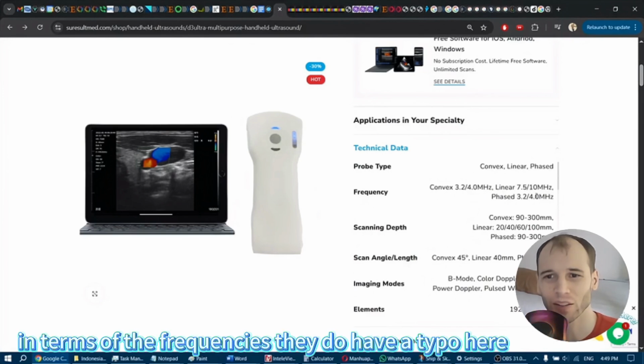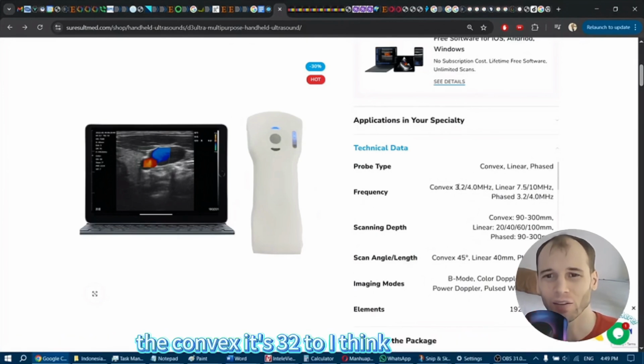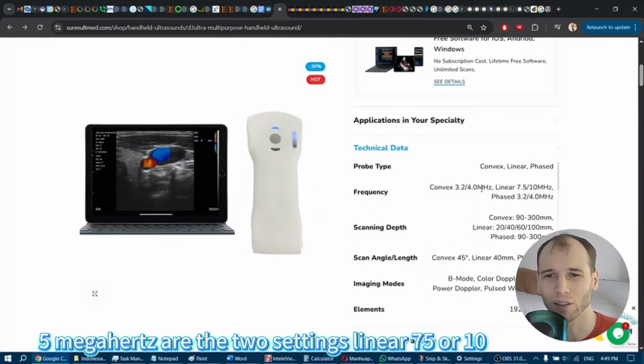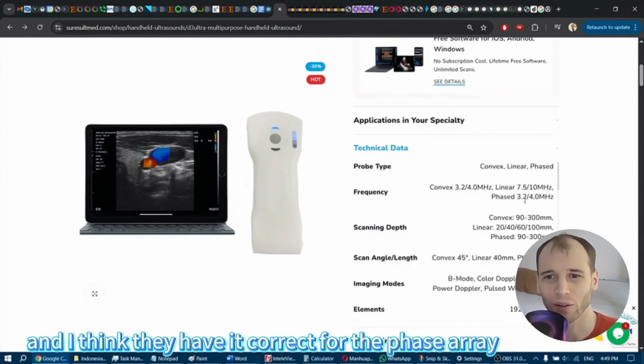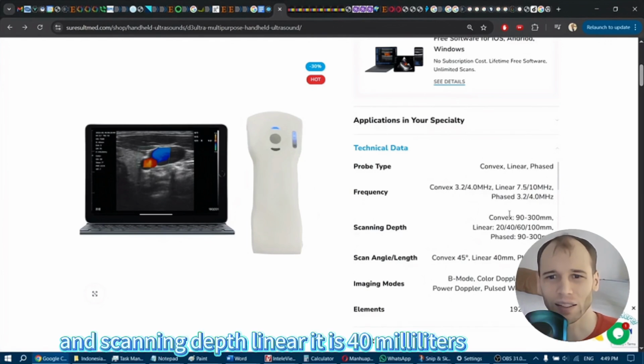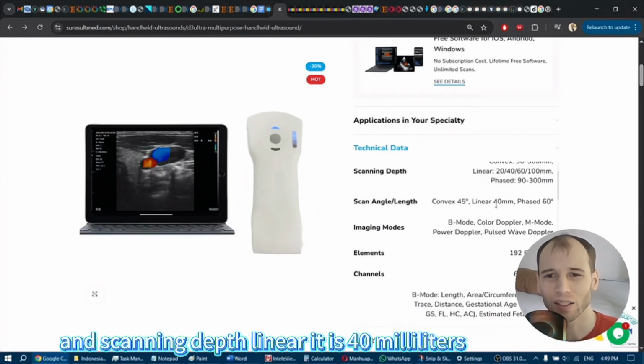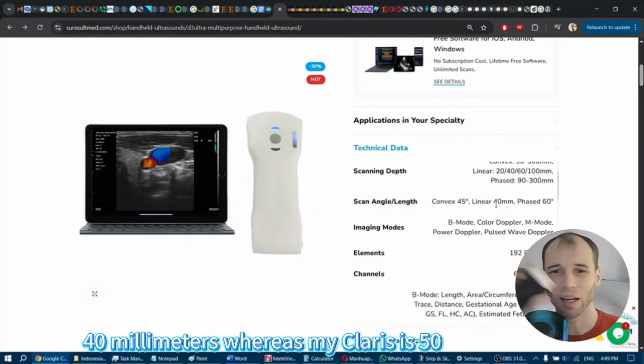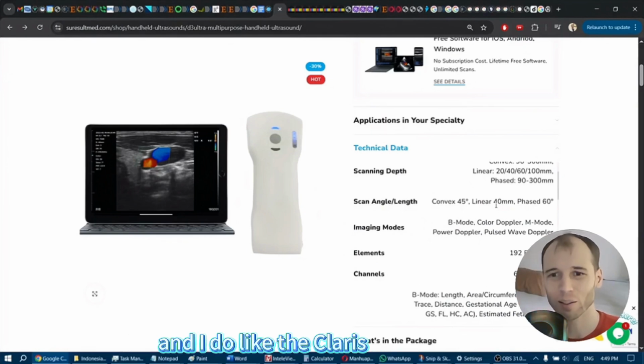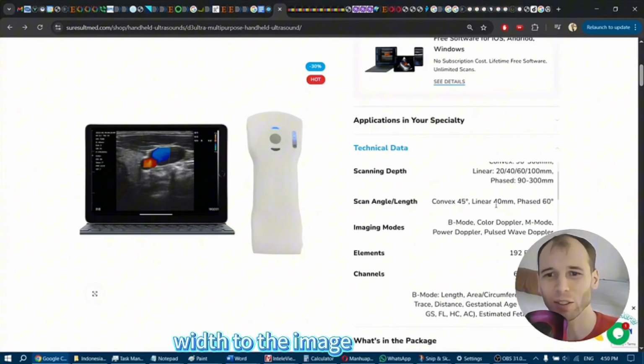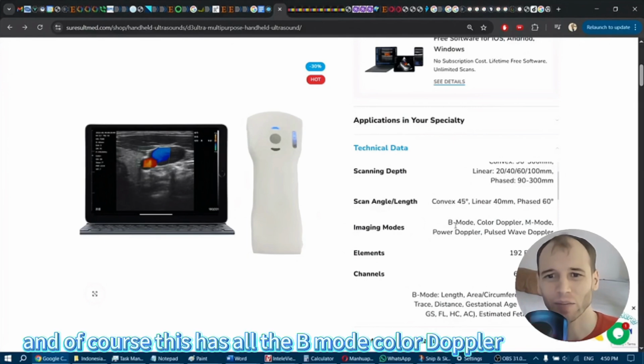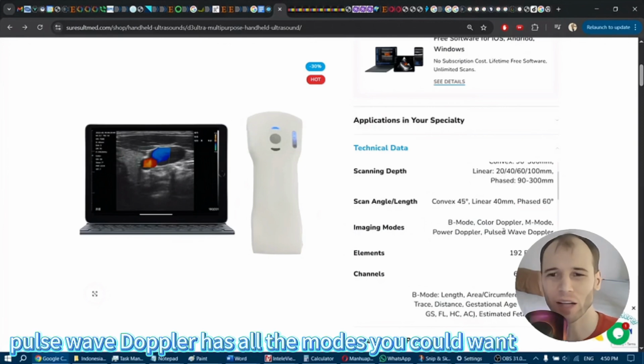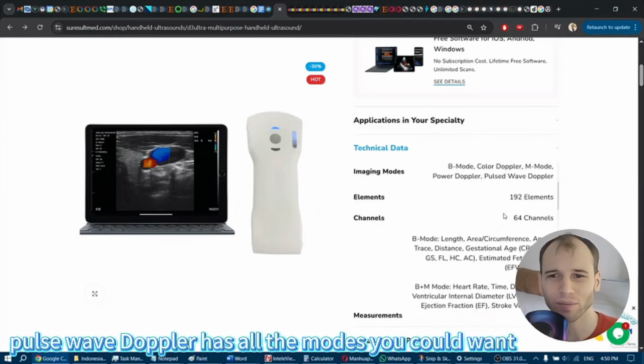And in terms of the frequencies, they do have a typo here. The convex, it's 3.2 to I think 5 megahertz are the two settings. Linear is 7.5 or 10, and I think they have it correct for the phased array. And scanning depth, linear, it is 40 millimeters, whereas my Clarius is 50. And I do like the Clarius because it's a little bit more width to the image, but you get what you get. And of course, this has all the B mode, color Doppler, M mode, power Doppler, pulse wave Doppler, has all the modes you could want.